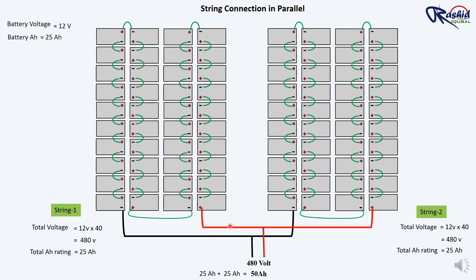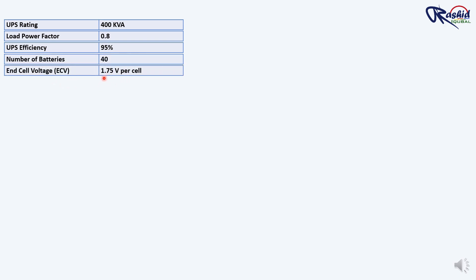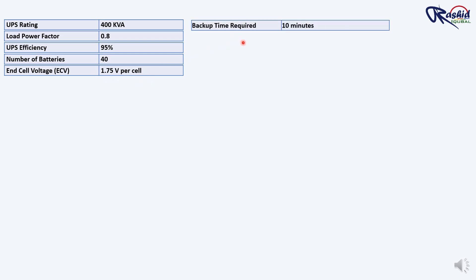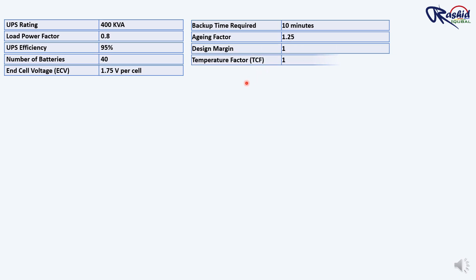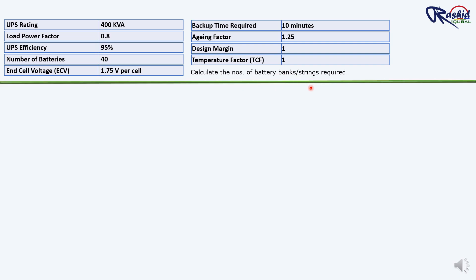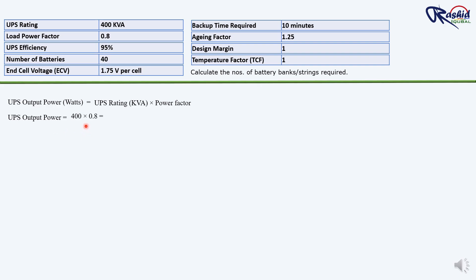Now we will learn how to calculate proper battery size and battery bank for the UPS. Example inputs: UPS rating 400 kVA, load power factor 0.8, UPS efficiency 95%, number of batteries 40, end cell voltage 1.75V per cell, backup time required 10 minutes, aging factor 1.25, design margin 1, temperature factor 1. First, we convert UPS rating into watts: UPS output power = 400 kVA × 0.8 = 320 kW.